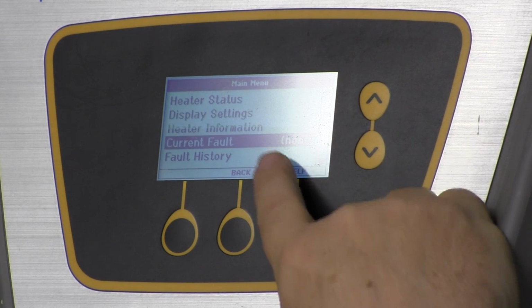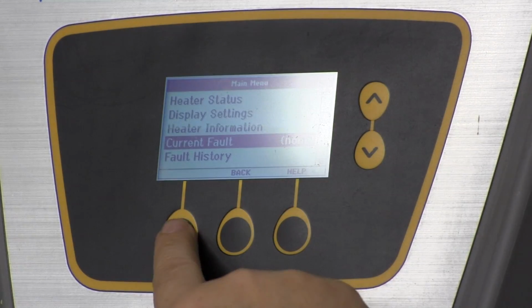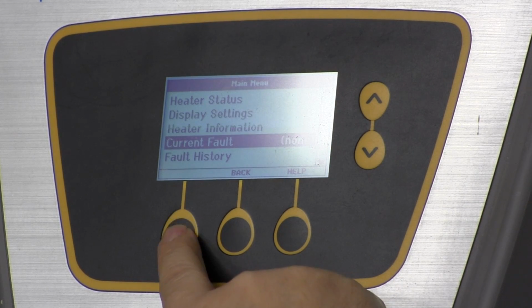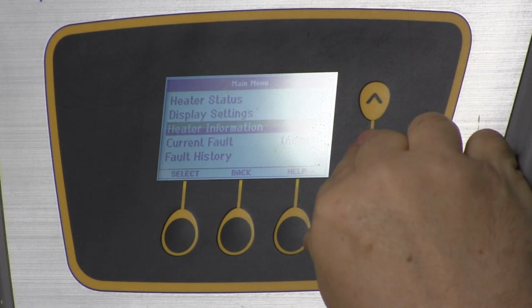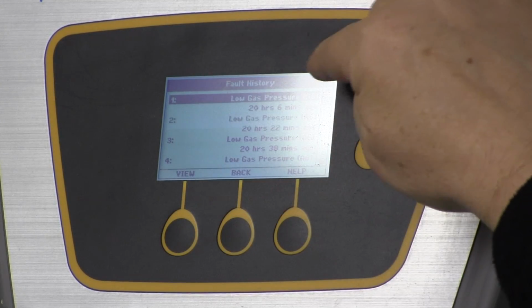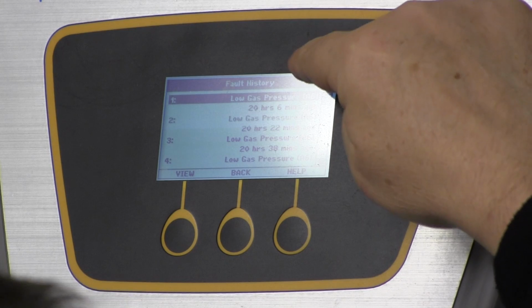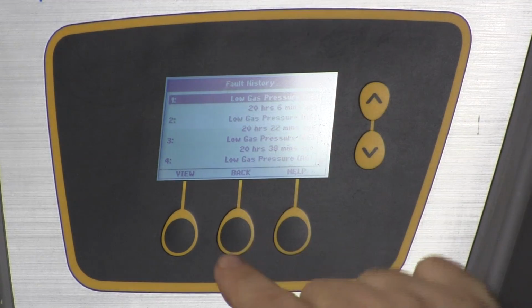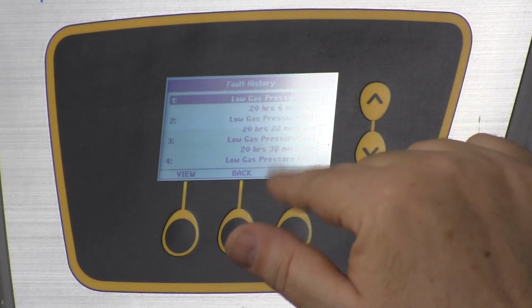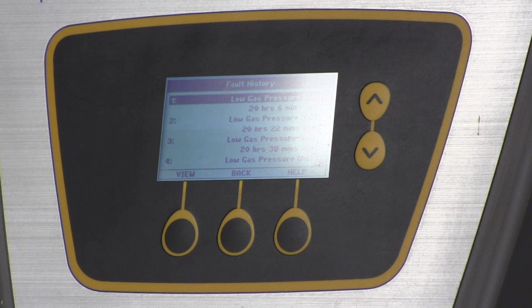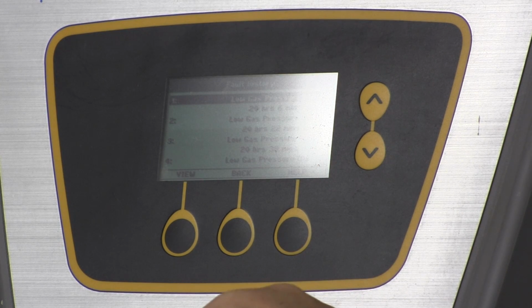And then current faults, or none, it'll show you the current fault. And then it'll have a fault history here. It'll tell you the faults, and you've had some low gas pressure faults 20 hours ago. So 20 hours ago, something happened to the gas of this heater, and it tried to fire 3 times, because it will try before it goes into lockout. You have heaters that will try once, then you have heaters that will try multiple times. The one time from a maintenance standpoint is kind of a pain. So it tried to fire 3 times, and then more than likely it went into lockout. Someone had to come down here and hit the button. So they hit the button, it turned on and off.